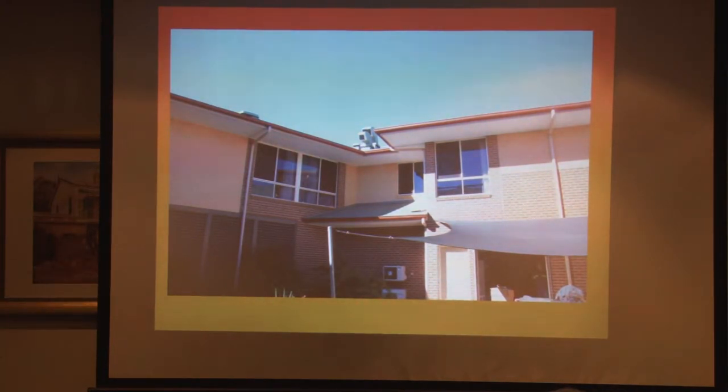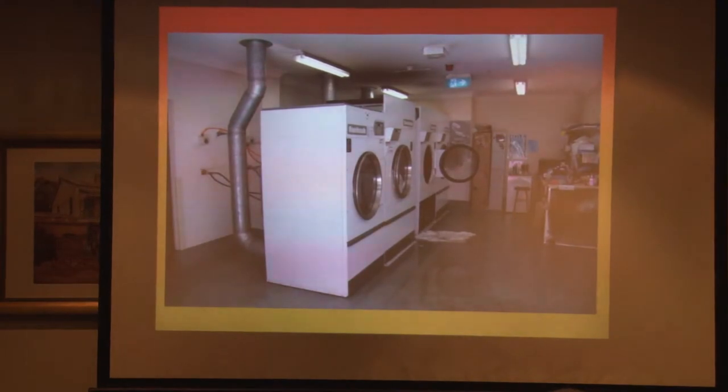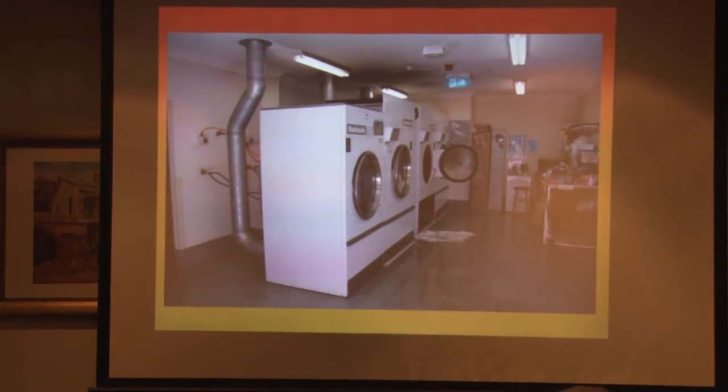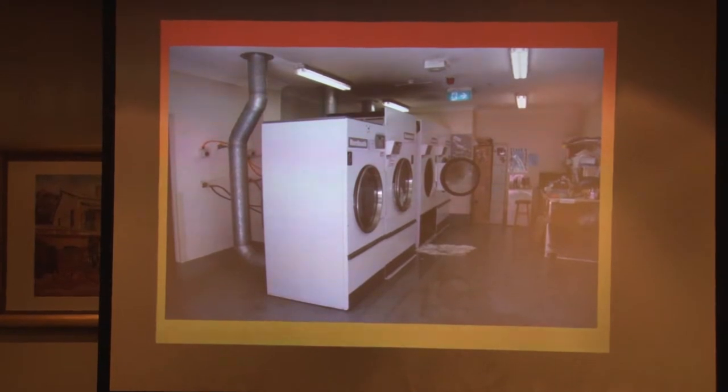While we go through this, just think of all the systems failures you've encountered and we'll go over those again. The fire was in a bank of two dryers — you can see the fire was in the one with the door open. You can see above the dryer that there's staining in the roof. It wasn't hot enough to actually set off the sprinkler system, but it did set off the smoke alarms and closed the smoke doors in the units above.